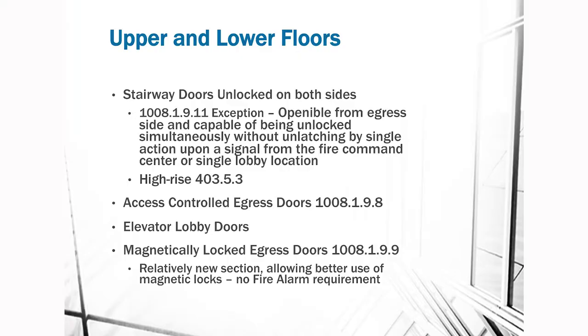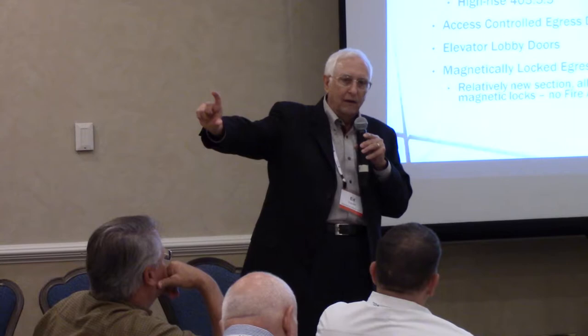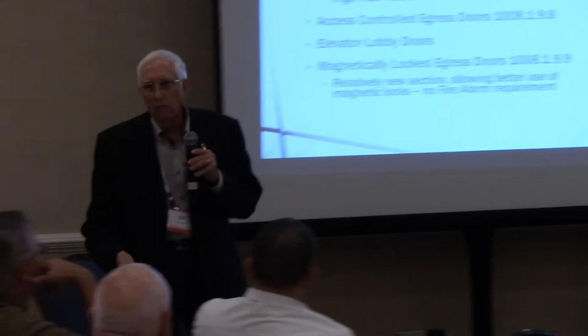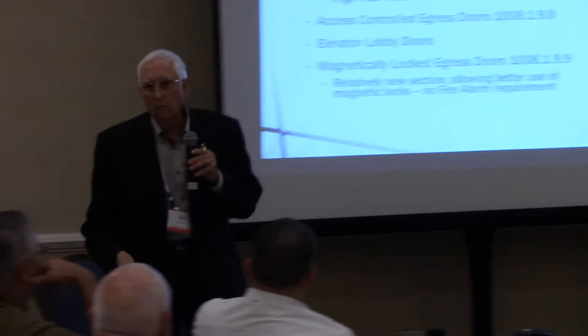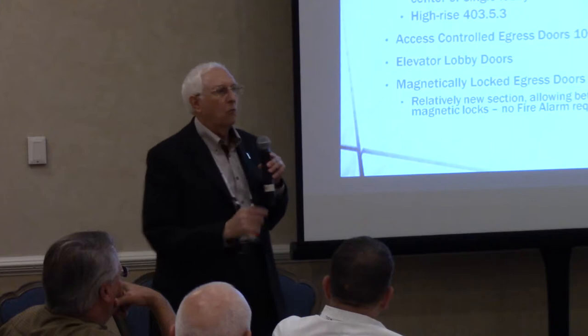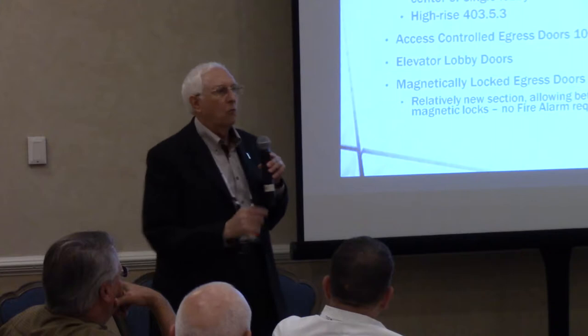There's also the access-controlled egress door concept when dealing with an elevator lobby, because that's not a stairway door — it's different. Usually that switch is tied to the fire alarm. When you're designing with an access control system you now have two fire alarm outputs that do different things — not one. You've got to deal with both. By having it on a manual switch, someone could pull the fire alarm on floor three and use that to gain access to floor six.